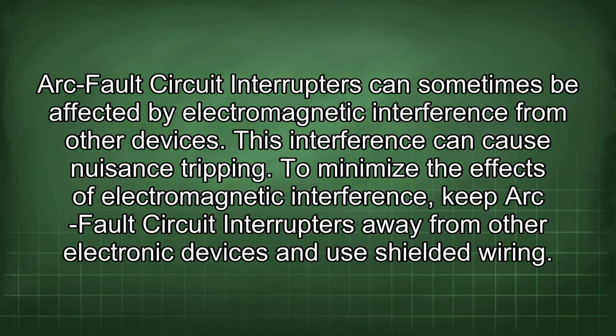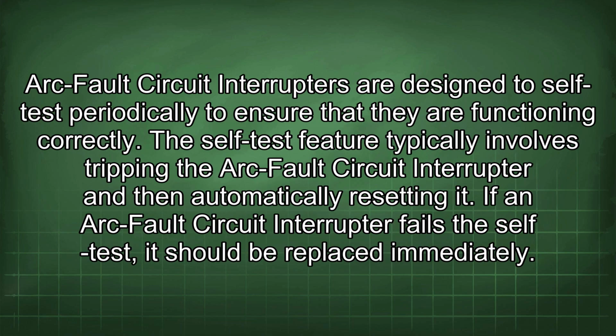Arc fault circuit interrupters can sometimes be affected by electromagnetic interference from other devices. This interference can cause nuisance tripping. To minimize the effects of electromagnetic interference, keep arc fault circuit interrupters away from other electronic devices and use shielded wiring. Arc fault circuit interrupters are designed to self-test periodically to ensure that they are functioning correctly. The self-test feature typically involves tripping the arc fault circuit interrupter and then automatically resetting it. If an arc fault circuit interrupter fails the self-test, it should be replaced immediately.